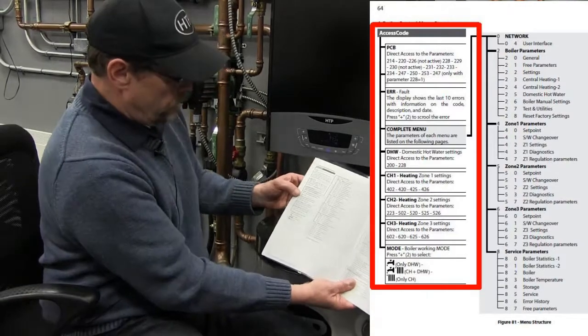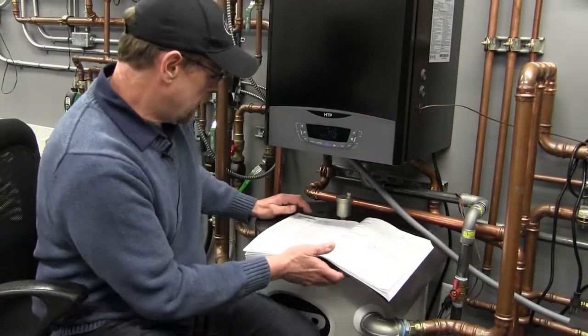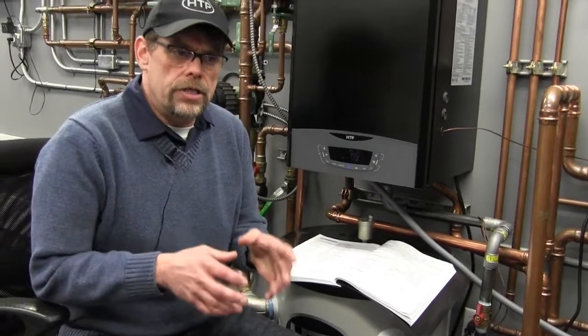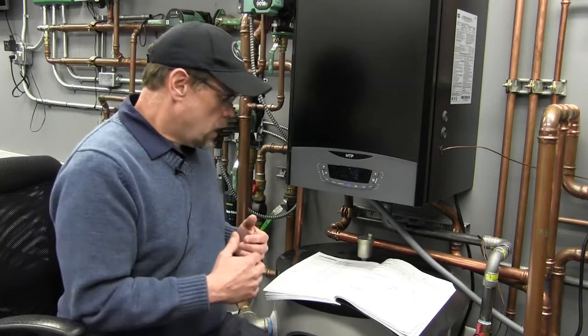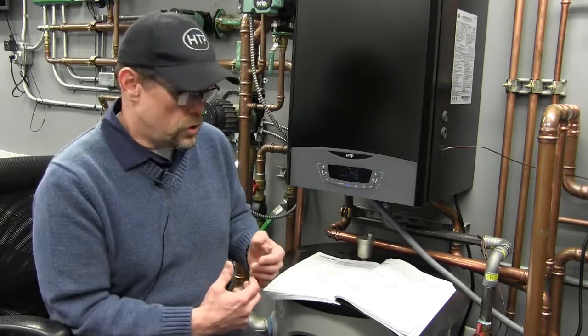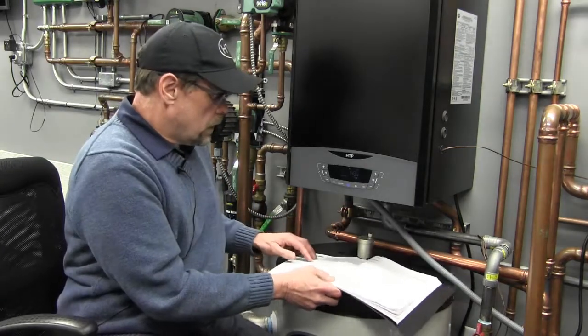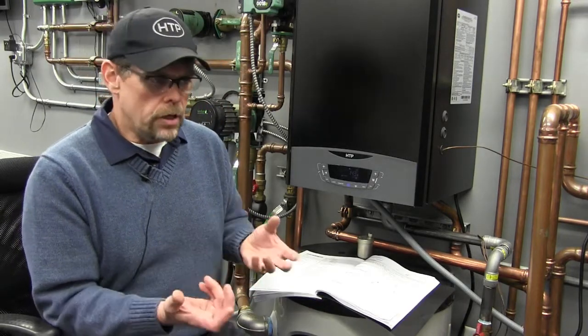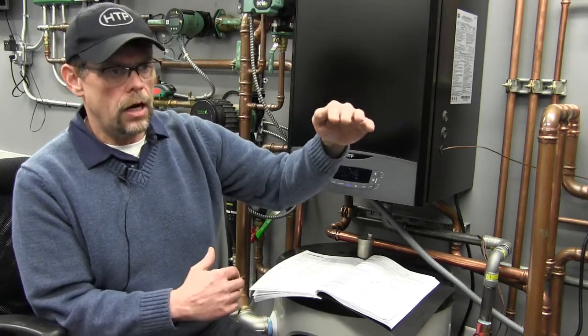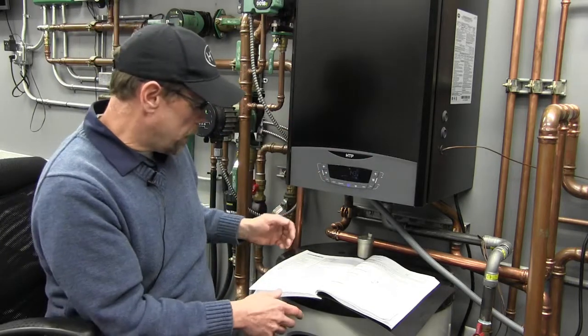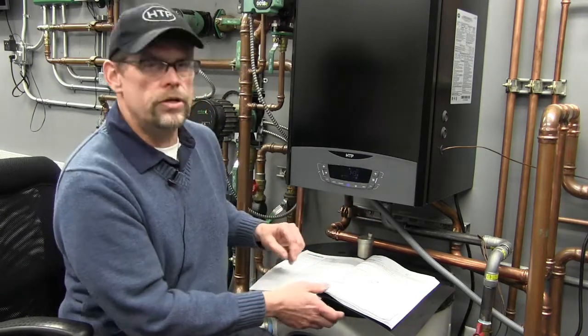Now, as we look a little further, we have CH1, CH2, and CH3. If I may make reference to that, CH1 is typically zone 1, and in a logical sequence, it would typically be your highest temperature zone should you have a multiple temperature system. So maybe zone 1 would be the fin tube baseboard zones. When we go down to CH2, CH2 is a second temperature zone, typically reserved for a sub-temperature. So zone 1 logically will be our highest temperature zone. Zone 2 will be lower than zone 1. The control logic will always shoot for the highest temperature calling. So again, make sure that if you are using CH2 as a sub-temperature zone, that zone needs to be protected by injection or mixing or some way to reduce the output temperature.